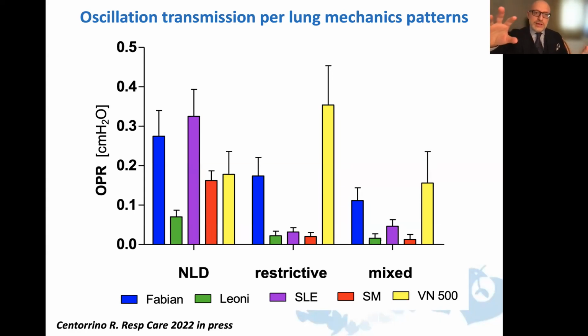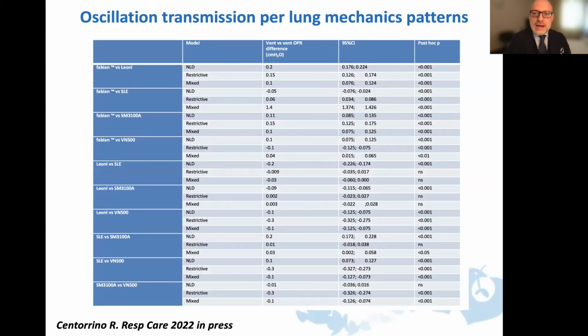other studies, because here we are looking at the transmission overall, you know, mixing a bunch of different possible parameter interactions, while in other studies they only measured the tidal volume or the oscillatory pressure at the given point with some particular parameter combinations, and we knew that the VN was not able to achieve the strongest, the more aggressive parameter combination. But here we are giving a full bunch of data, and we are investigating the ventilator performance on a full bunch of parameters. So sort of a very much pragmatic real-life test, taking into consideration all the parameters that you may want to use at bedside. And those are the raw data behind the graph that I just showed you.